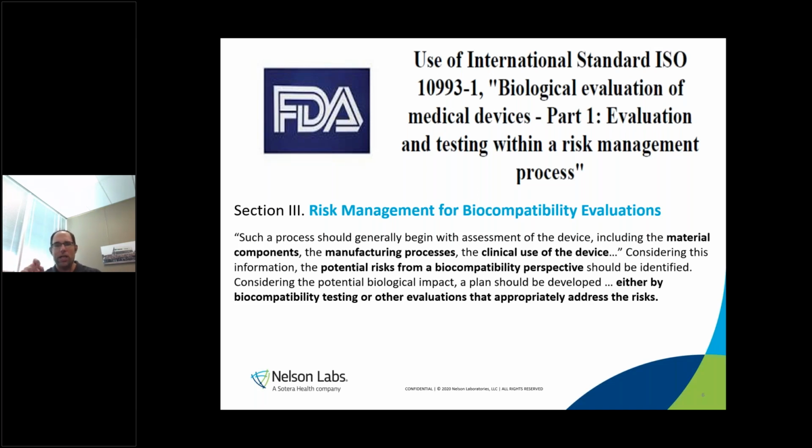So when you're looking at your changes, you still follow those formulas. You look at the materials. Have you changed any of the materials, right, with your change? And this is patient contacting, either directly or indirectly, materials. Have you changed any processes that could impact those materials? Have you changed the intended use of your device, which sometimes they add another indication, right? So we have to look at that gap. So those three things, inputs, go into your risk assessment. And based on that, you can either look at the risks and then identify if there's testing needed or if we feel confident in the assessment.